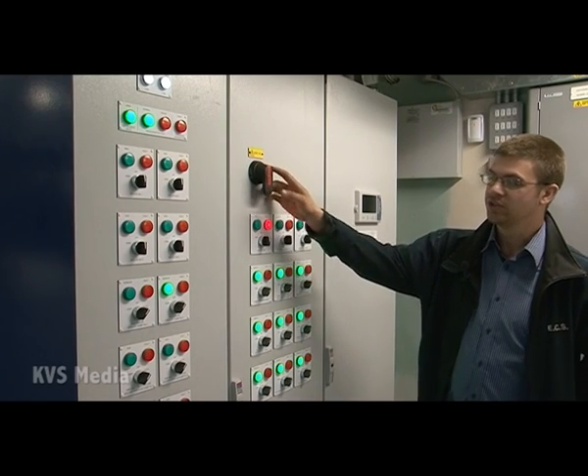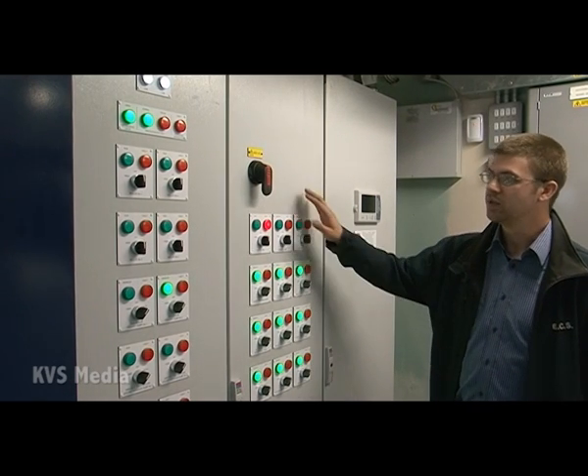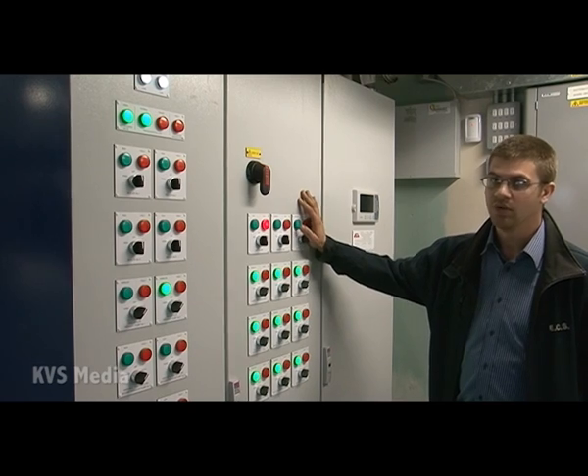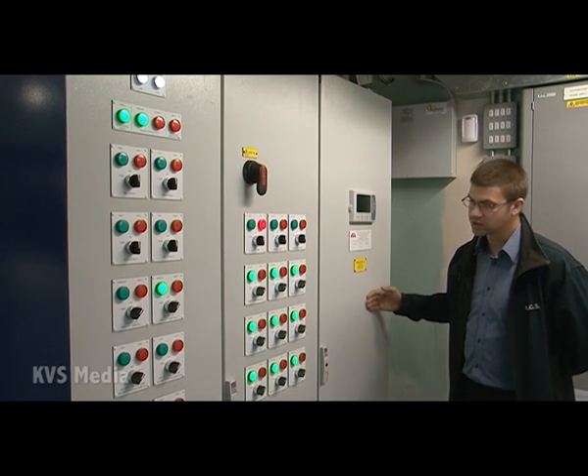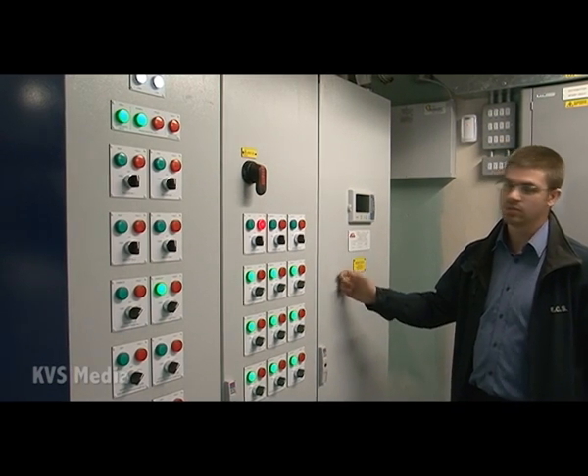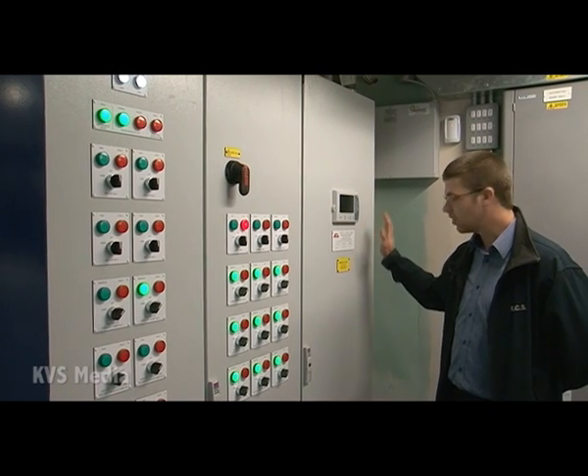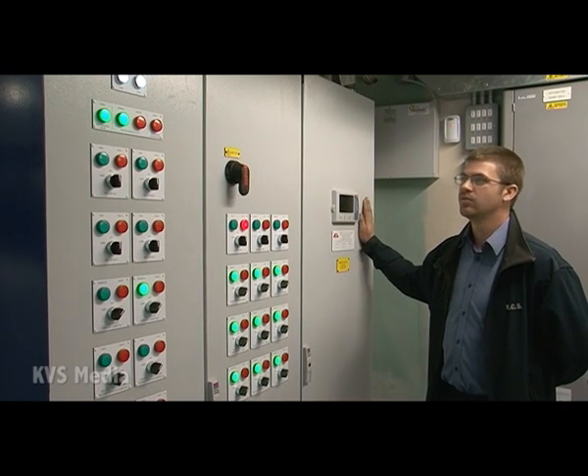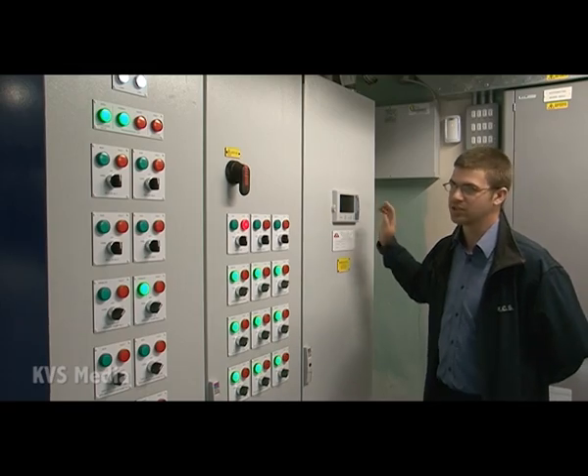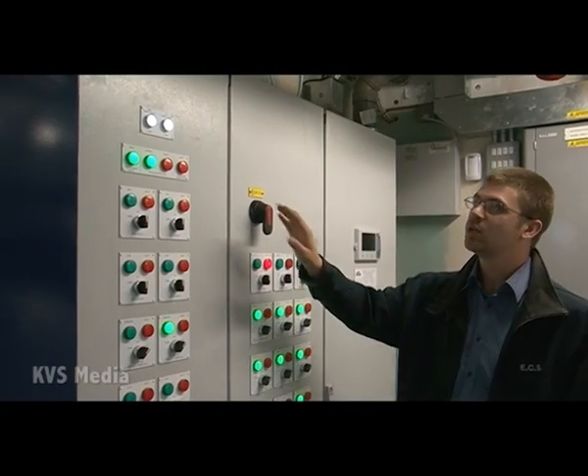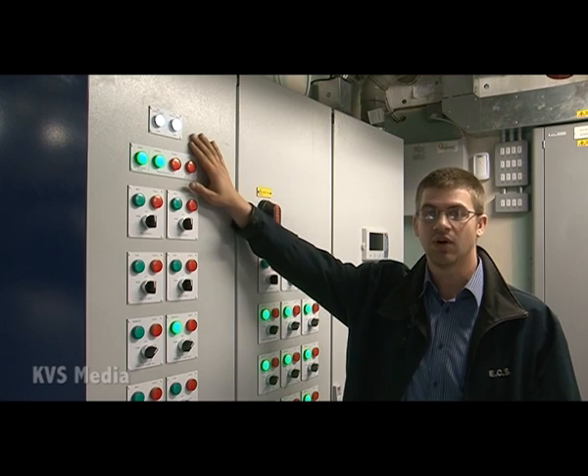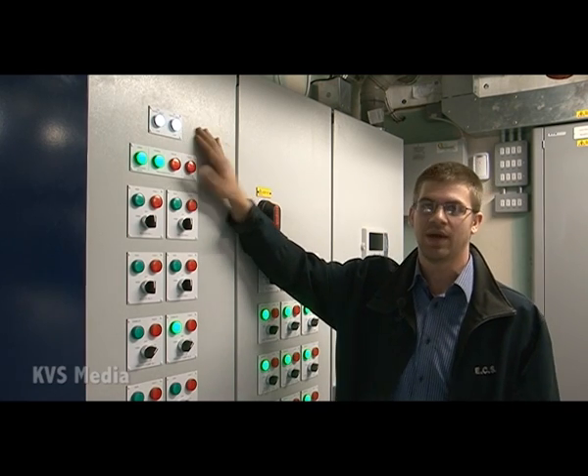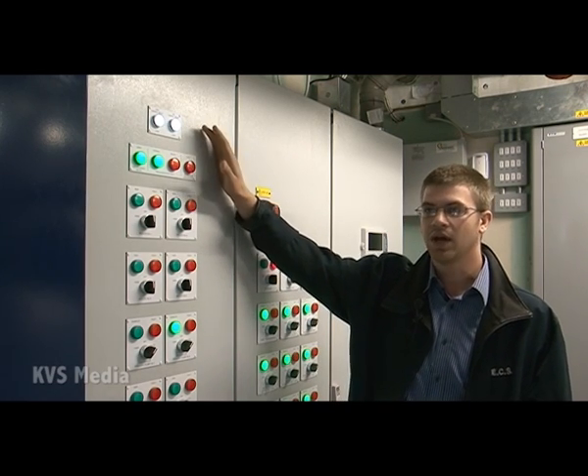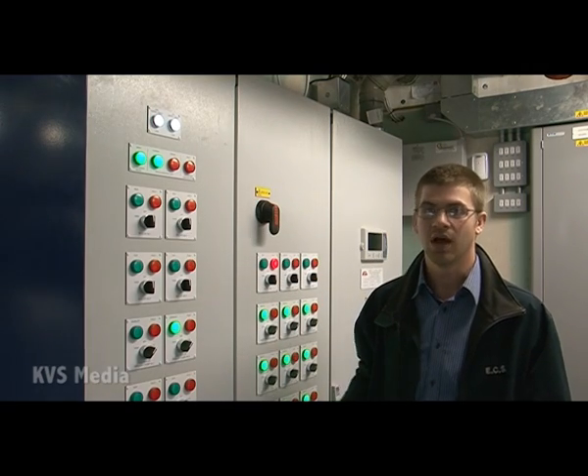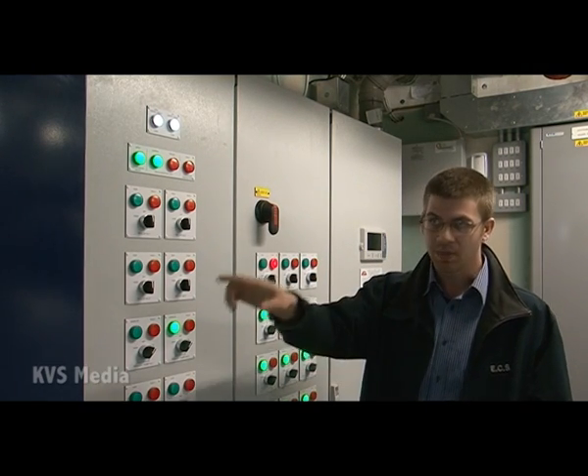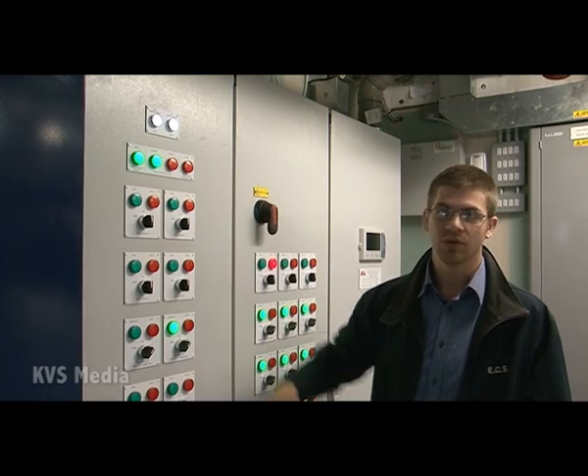It's door interlocked, so you cannot enter this compartment with everything on. This section isn't door interlocked, allowing our engineers to get inside with everything energized, but like I said, it's low voltage, so there's a reduced risk of electric shock. So those white lights indicate that the control circuit is on, live and healthy. They will only go out in a serious failure, power cuts, or if a fire alarm has gone off. There's a knock-off button by the door which will shut all of this down.